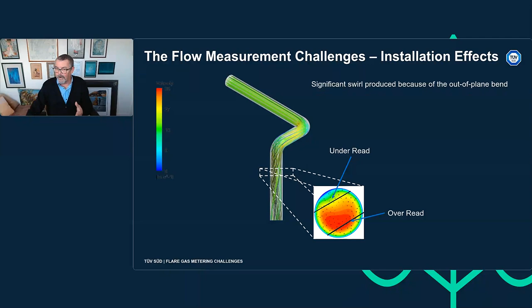We can then move on to proprietary calculations. Again, I fully understand intellectual property, and I have great admiration and respect for the people who have developed these calculations that have allowed the industry to calculate mass and standard volume flow without a live gas composition. It's an incredible piece of work. So proprietary calculations are not bad in and of themselves, but in the changing landscape, as we adopt a fiscal mindset for flare metering, there are challenges there. By their very nature, they're extremely difficult to independently verify because you don't have any calculation details. That is the property of the manufacturer.